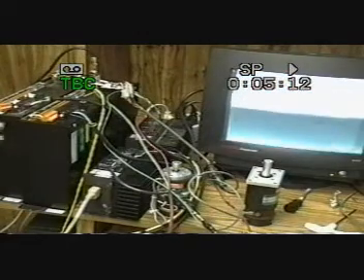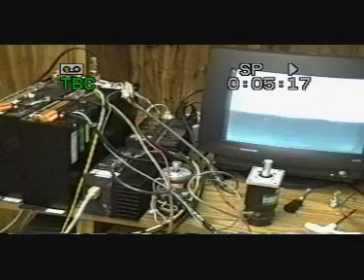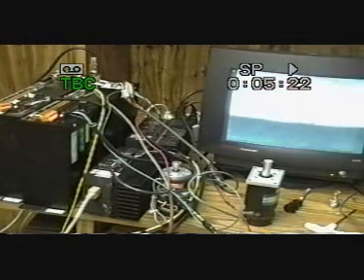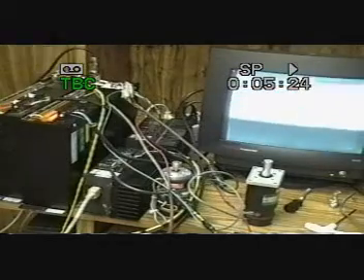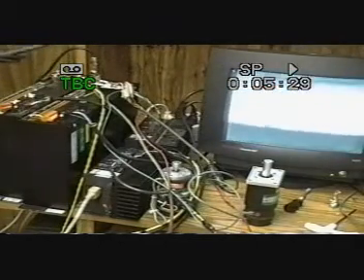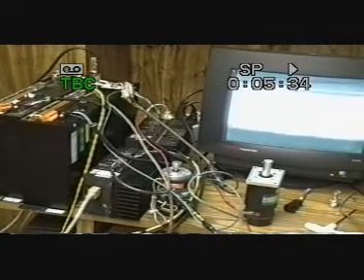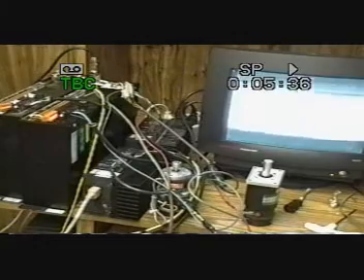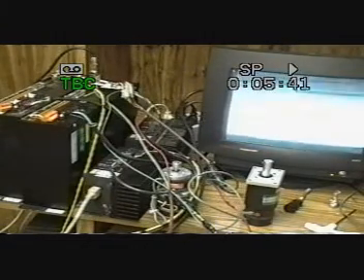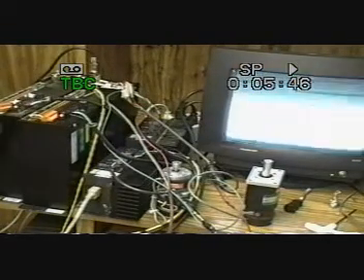I'm going to have to blame, and I think rightfully so, and I'll demonstrate it right now, that the encoder pulses coming from the emulator are degraded somehow. What I have here, instead of my test cable, which is fully shielded, this is a standard video cable, 15-pin sub-Ds, and if you test pin to pin, you do see that you do have the conductivity, but the shielding is all wrong. With a quadrature encoder, it's very important that we have the shielding correct.